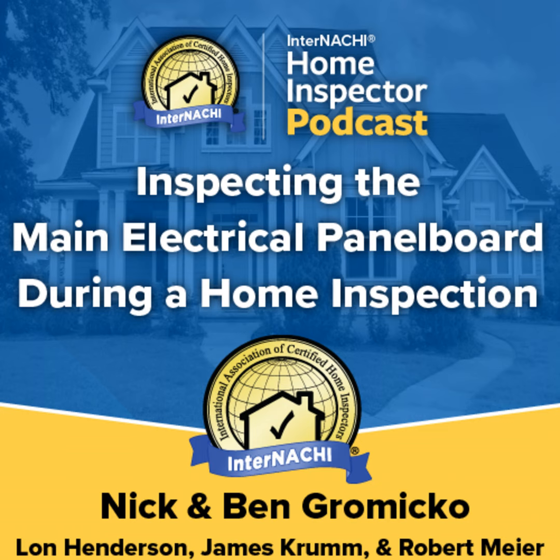Double-tapped neutrals. The grounded conductors, commonly called neutrals, are the white wires inside a residential electrical panelboard. Only one neutral wire is permitted to be connected under one lug of the neutral bus bar. Panelboard neutral bus bars are usually not listed for use with more than one wire per terminal.